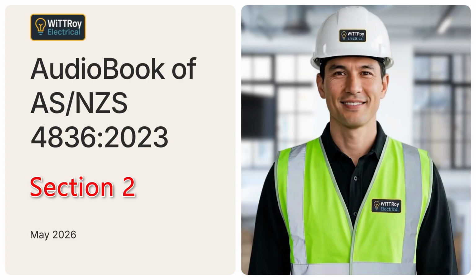Clause 2.1. General. Clause 2.1 explains the basic rule before work starts. Before anyone works on or near an electrical installation or electrical equipment, a competent person must determine whether it is safe to do so. This is done by using a risk management system. All work must be planned and organised to minimise the risk connected with the work. The most effective way to control a risk is to remove the risk completely. In electrical work, this often means de-energising, isolating, securing the isolation, and proving the equipment is de-energised before work begins.